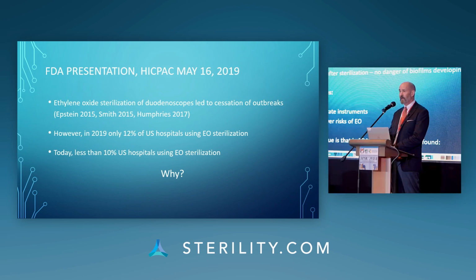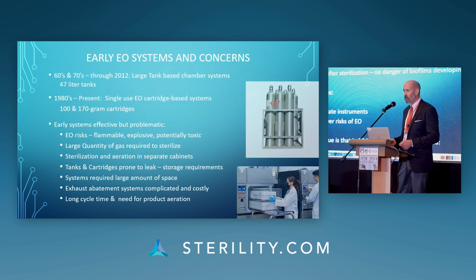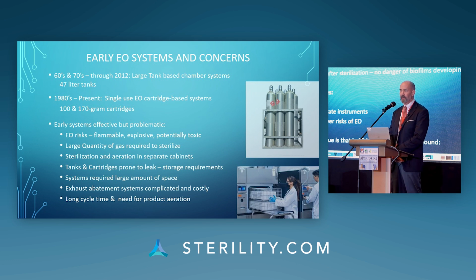However, back in 2019, FDA discovered that only about 12% of American hospitals were still using ethylene oxide. Today, the number of US hospitals that have ethylene oxide available to them is less than 10%. And the question is, if this is such an effective sterilization method, why is it falling into disuse? And for that, we have to look at some of the early ethylene oxide systems. And for many of you here, you're going to be familiar with these issues.